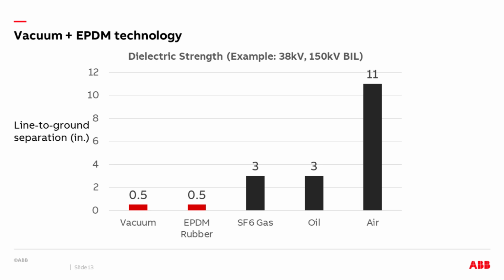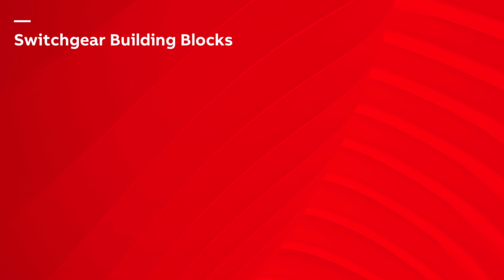So finally, I show this vacuum plus EPDM technology chart where we compare line to ground separation for a 38 kV, 150 kV BIL example. And you can see that vacuum and EPDM rubber are down on the left at the smallest separation, which makes it a nice choice for an effective compact package for medium voltage switching. Air being the biggest distance required, no surprise there, but air has been an effective insulator ever since electricity was invented. The nice thing about air as an insulation choice is it's free, and without it, we wouldn't have all the overhead distribution we have today, and transmission for that matter.